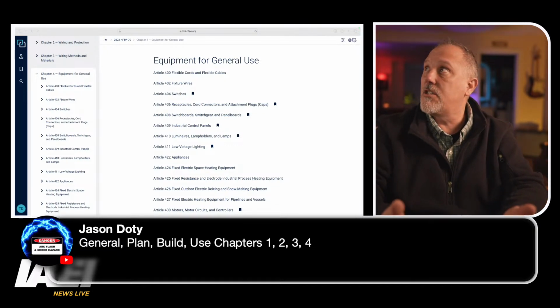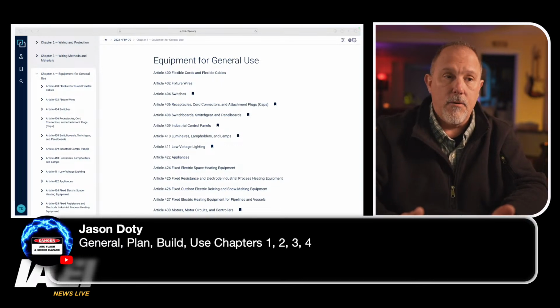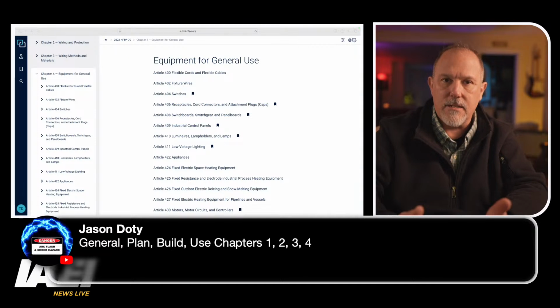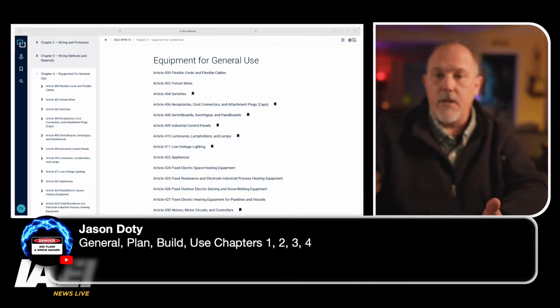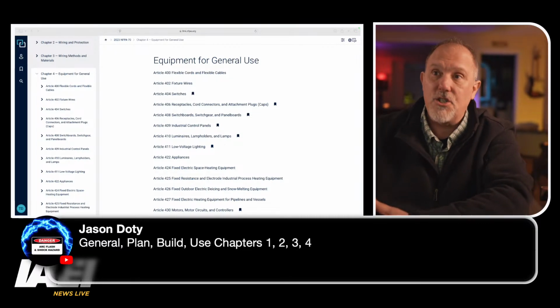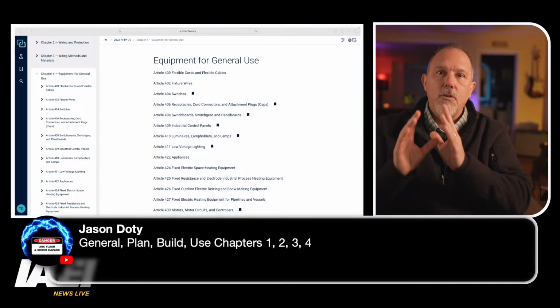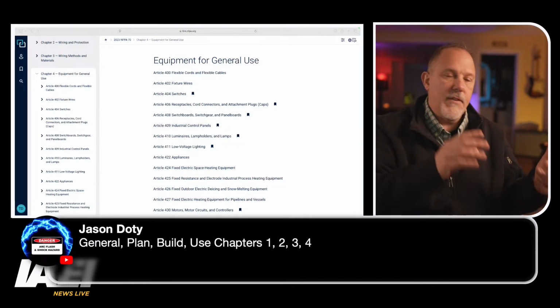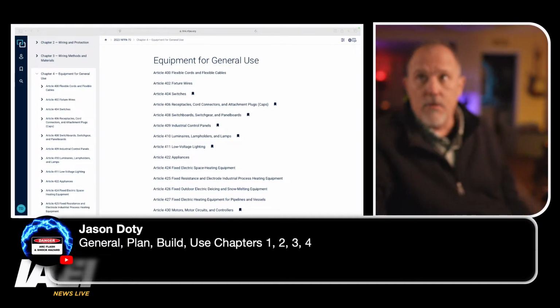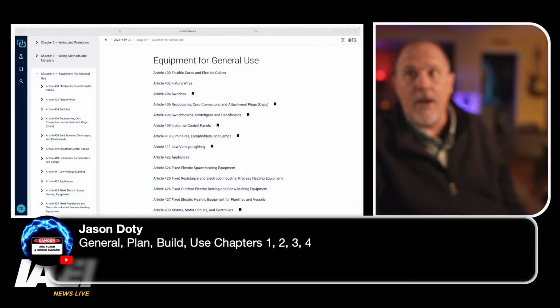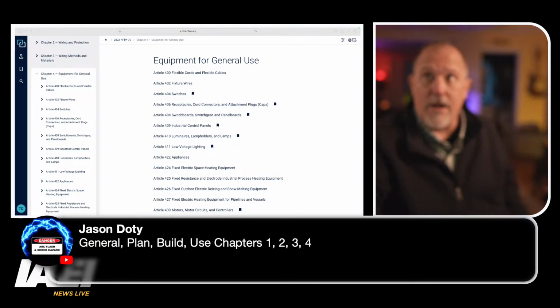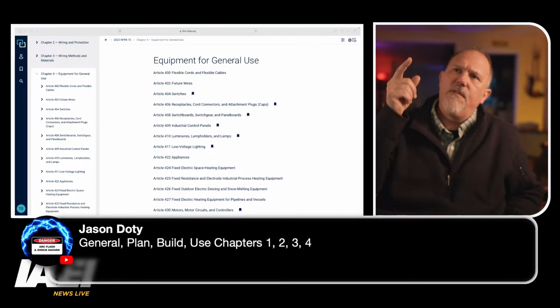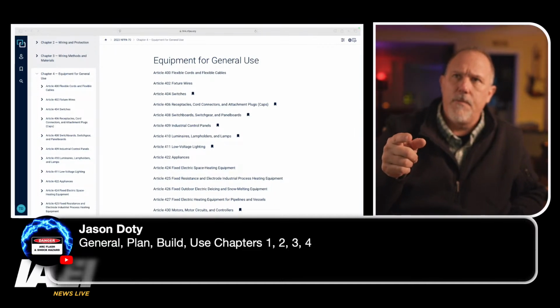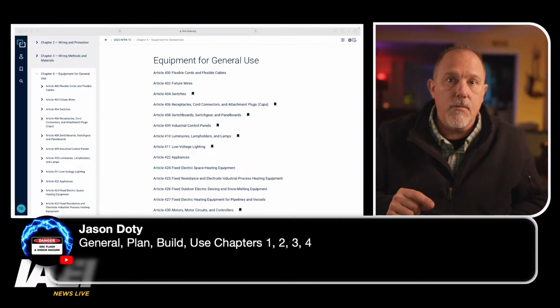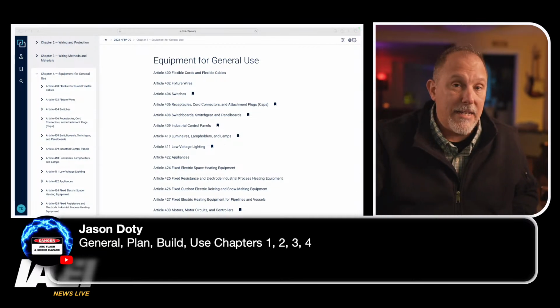Can I string it through the studs or joists inside my walls and ceilings? Then you determine if you have to put it in a raceway, and what raceway you're permitted to use in that application. That's chapter 3 stuff. When you get to chapter 4, you're looking at the equipment itself, like a lighting fixture or luminaire, article 410. Then you have 402 fixture wires, 400 flexible cords and cables, and 404 switches. You might ask why flexible cords and cables are in chapter 4 and not chapter 3 — that could be a common mistake.